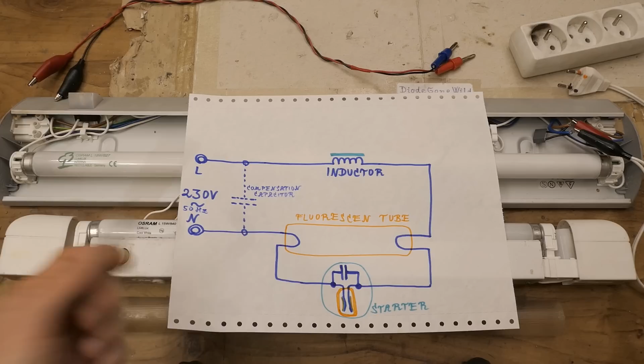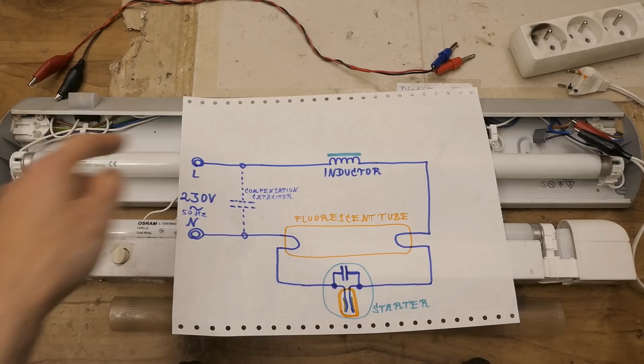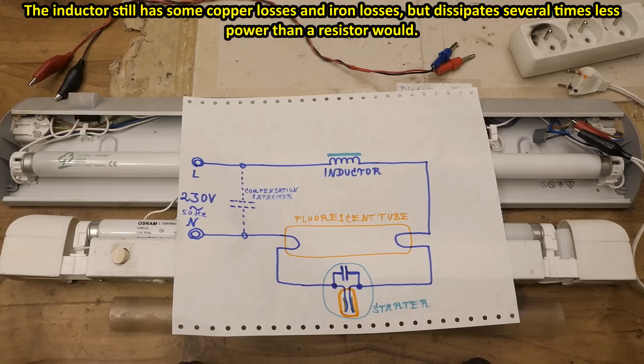Here is the inductor with an iron core, limiting the current of the lamp or fluorescent tube, because the discharge basically has a certain voltage drop, which actually goes a little bit down with more current. It has a negative resistance, so it can't be connected straight to mains, and using an inductor to limit the current is less lossy than using a resistor in series.